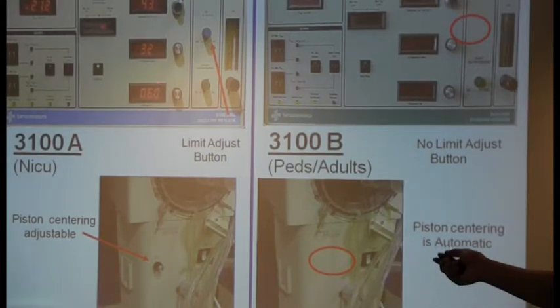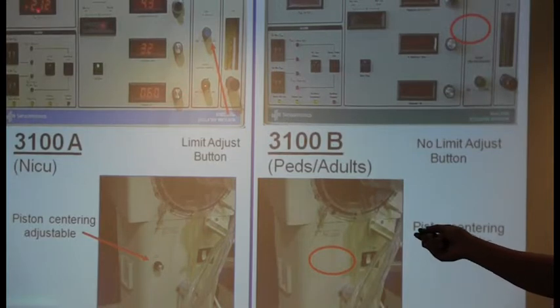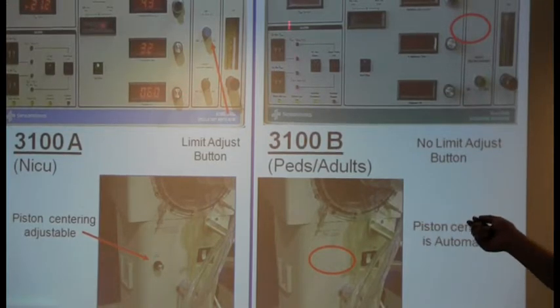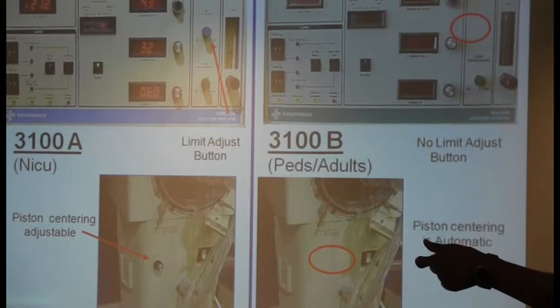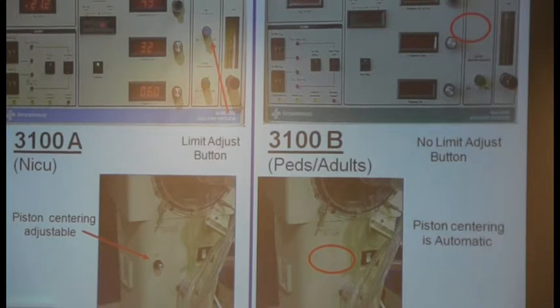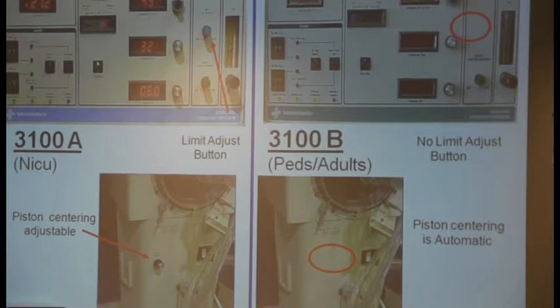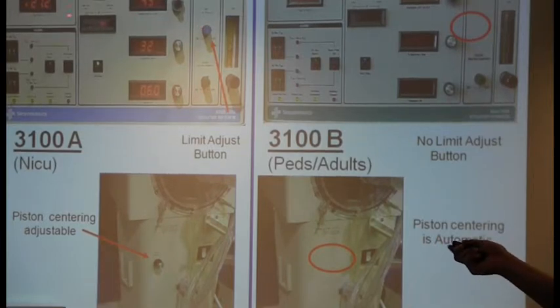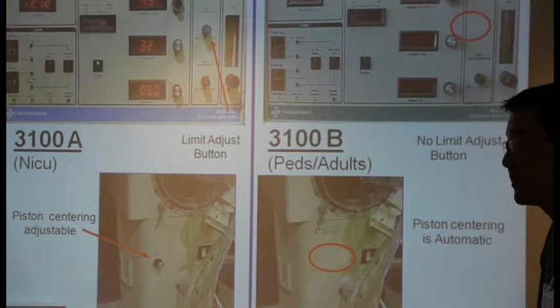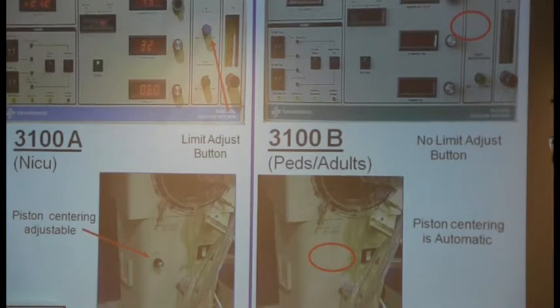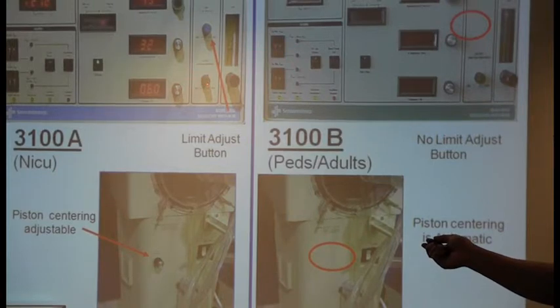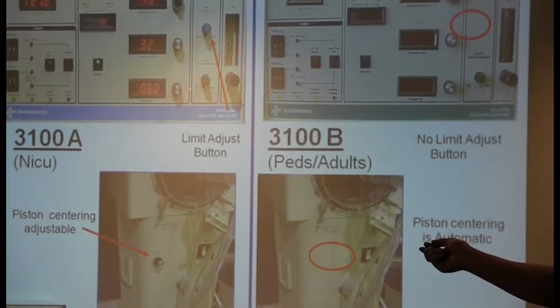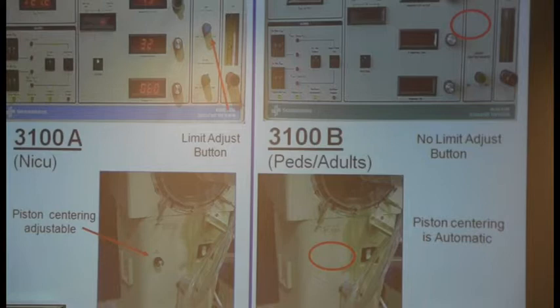20, because remember, my green knob, where it's set, is at 21. But my limit knob, as I turn it down, says 20. So where's my pressure limit? 20. Okay. So now what you do after that is you want to go one more below, to 19. So you keep turning this to 19. At 19, what's my limit? 19. What's my adjust button set at? 21 originally. Okay, so here we go.